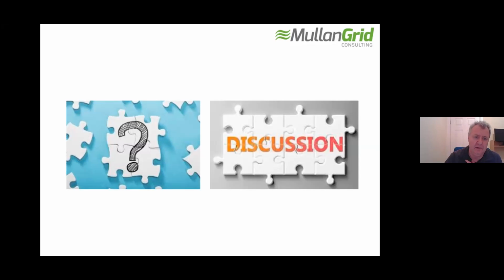Yeah, just a follow on from that, a question just came in. Export limiting schemes are sometimes used in the UK. Any clue how this may be applicable in the Irish context? Well, for the likes of zero export projects, you're not allowed to export, so you have to put in some sort of throttle or zero or limiting scheme. Basically you put a sensor at the export point to make sure you never export through it. You put some CTs there, and that feeds back into your power controller that's communicating with your inverter for solar or with your wind turbines. So you basically have to throttle back to ensure you don't export if you have a zero export scheme.